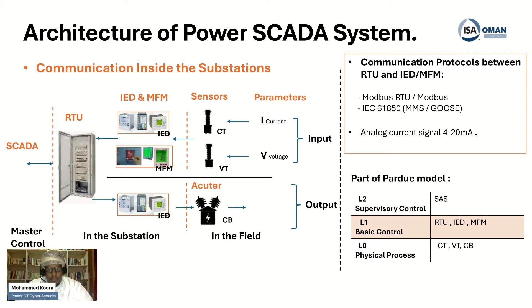Let us go further into IEC 61850 for power substations. What is the benefit of this protocol? From this chapter, I need you to understand that this protocol enables very fast communication—we're talking milliseconds—and it helps equipment like IEDs and numerical relays from different vendors understand each other, sharing the same language. They can communicate with each other; we call this interoperability, so there is no monopoly from one vendor or OEM.